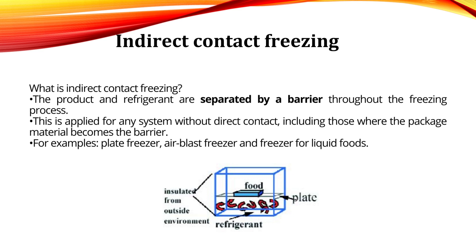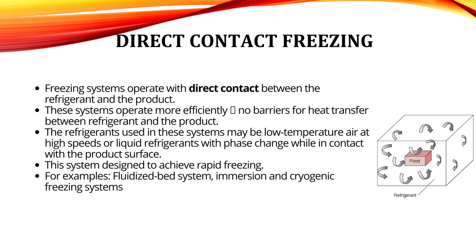Indirect contact freezing is a process where the product and refrigerant are separated by a barrier; packaged material can also serve as the barrier. Plate freezers, air blast freezers, and freezers for liquid foods are examples of indirect contact freezing. Direct contact freezing is designed for rapid freezing and operates with direct contact between the refrigerant and the product, making it more efficient since there is no barrier. Examples of direct contact freezing include fluidized bed systems, immersion, and cryogenic freezing systems.